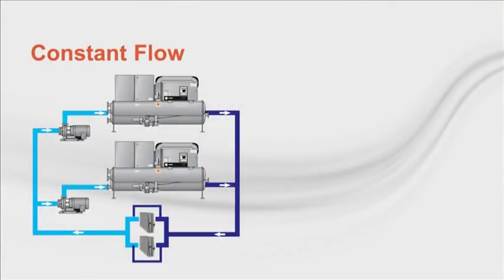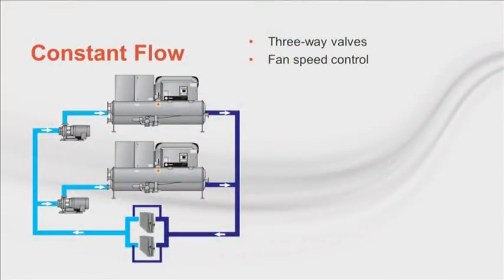Now, constant flow was common in the 1980s and earlier, and still works well for small chilled water systems, especially those with few coils and designed for the minimum chiller flow and highest DeltaT. Systems with multiple coils use 3-way valves to maintain constant flow throughout the system. It's a really simple system for the chiller, and because it has fewer components, the entire system can be easy to control, especially when there is only one chiller operating at any time. Systems may even be able to use fan speed discharge air temperature control instead of control valves in some instances.